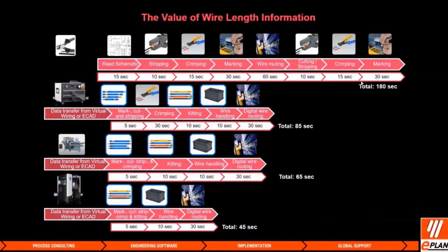We've done a lot of time studies, and I've certainly done some myself. If a wireman is able to land a wire every 3 minutes, that person is really moving quickly. So we're using a pretty conservative number here, but often customers will state it's closer to an average of 5 minutes. But utilizing some of our semi-automated equipment, we can start to reduce that time significantly, bringing it down to 85 seconds or even 65 seconds.